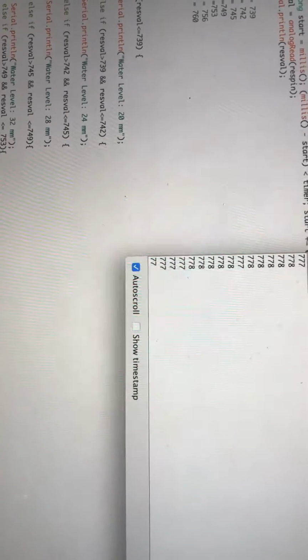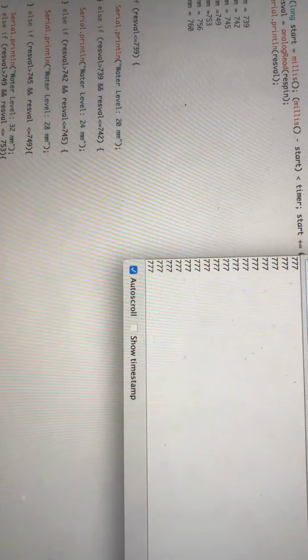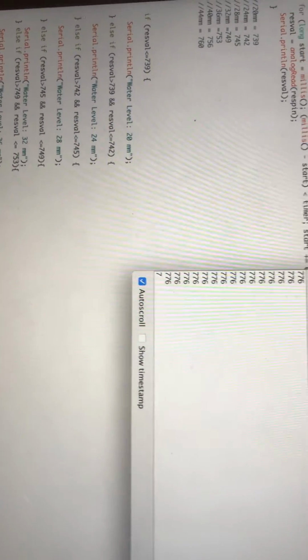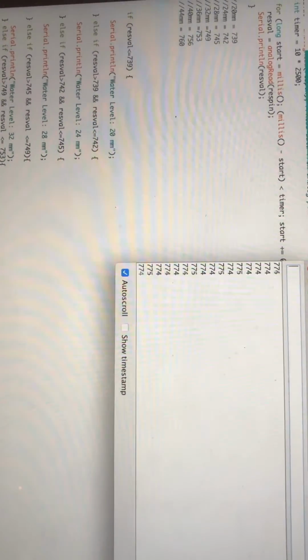I will now test the depth sensor in cold water to see how cold water affects the readings that I get. The calibration I'll be using will be that of the freshwater calibration. I currently have about 24 millimeters of water, as with all the other tests, to ensure consistency. These analog output readings are much lower than that of the hot water or the salt water, being much more in line with the fresh water at room temperature.